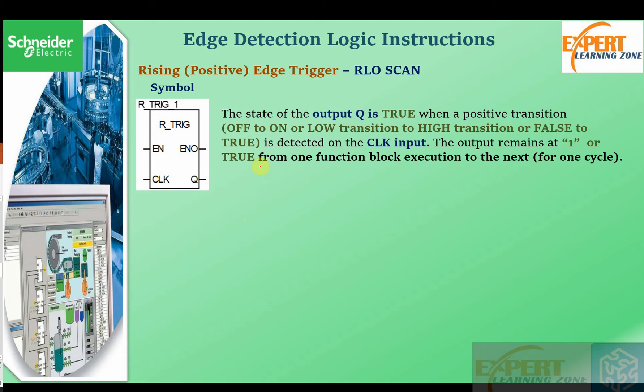The output remains one or true for one function block execution, that is for one clock cycle. If there is a change in the clock input from logic zero to logic one, then for one clock cycle the output is set to one. In the next cycle it becomes zero if there has been no change. You can put all the logic on the left side of the clock to evaluate a change from zero to one — that is why it is a logic output scan rather than an open scan as in the transition contacts.